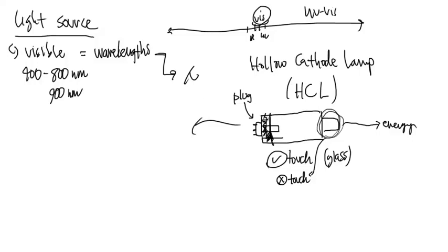On that label, there will be a number with nanometer after that number, or the symbol for wavelength after that number. That is telling you what the wavelength should be for the machine for your analysis. That number is pretty important.